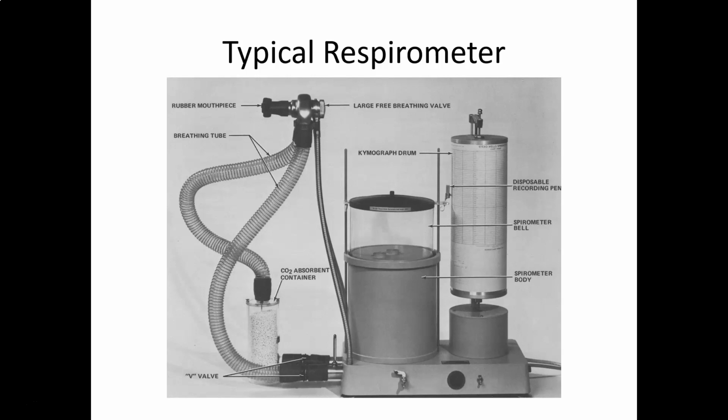And that's the pressure, and then the S is saturated. When we breathe out, air is typically saturated with water vapor. That water vapor takes up space and changes the volume of the gas that we have. So we have to standardize all that and make it equal with this BTPS correction factor.